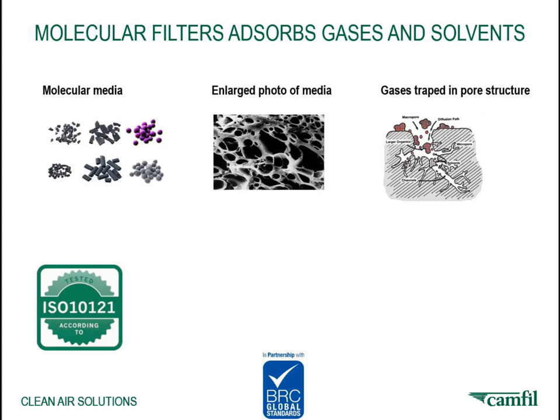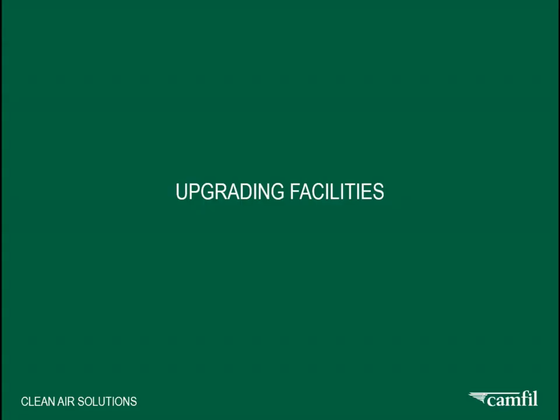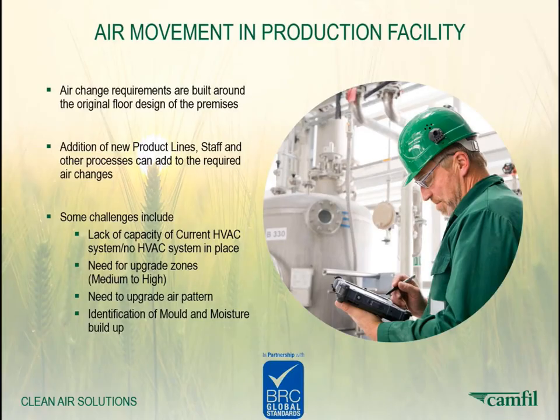Remember to always ask for the molecular test standard when considering molecular filtration, because there is also a standard available for that. If we look at upgrading facilities in a manufacturing plant, there is a lot of air movement, both uncontrolled and controlled. Air movement could be caused by openings between production and warehouses, in and outload, HVAC system, exhaust system, production equipment, and many more. Air change requirements are often engineered when building the facility, but not always updated. Additional new product lines, staff, and other processes can add a need for new required air changes.